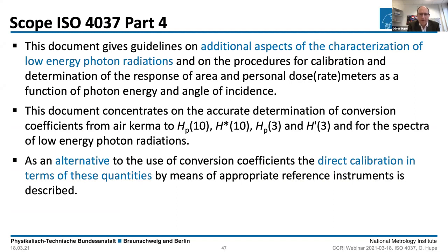So that's the reason that this part 4 mentions this again. And this starts already if you have an N-20 quality and you have 75 degrees angle of incidence. It is nearly impossible to achieve the accuracy to adjust the angle of incidence. So I invite you to have a look at part 4. There's a table with the requirements, and it's really fascinating.